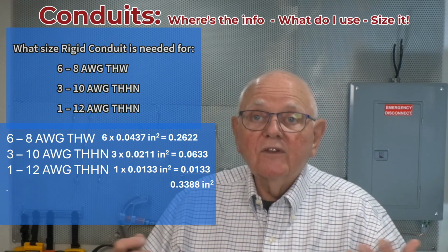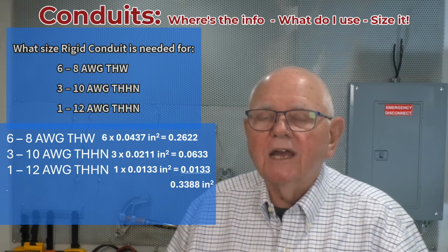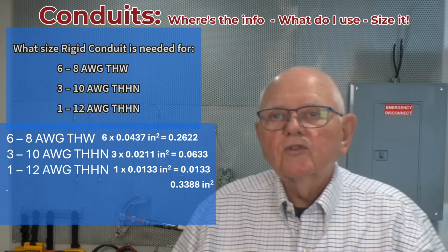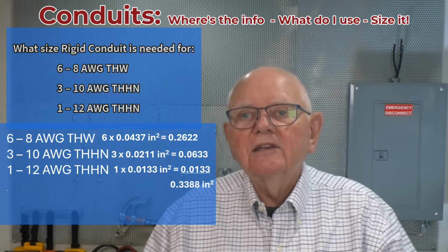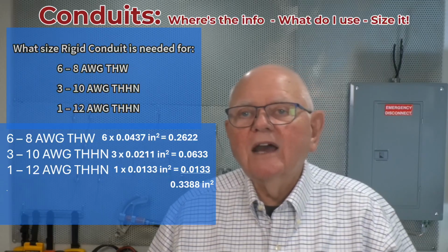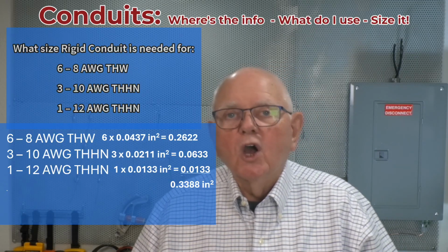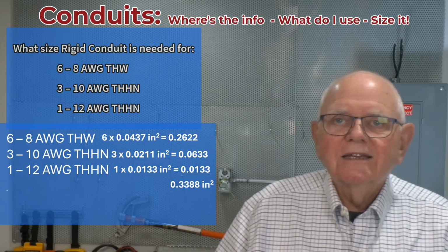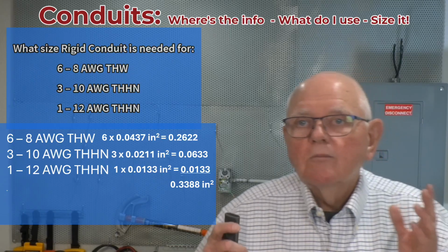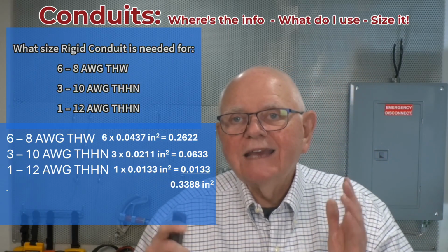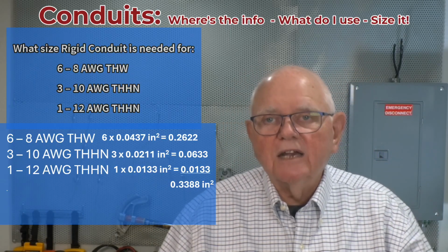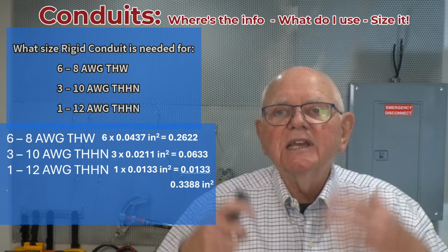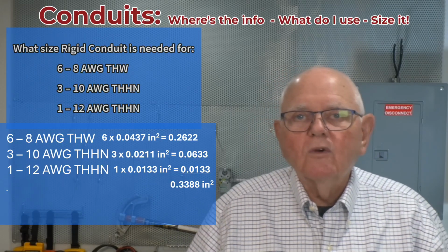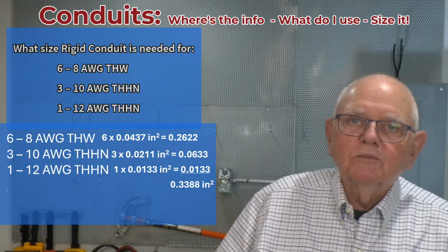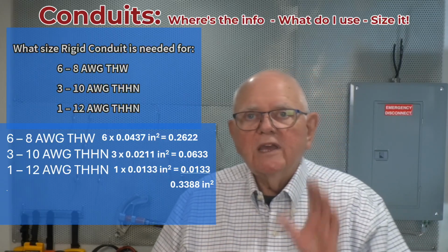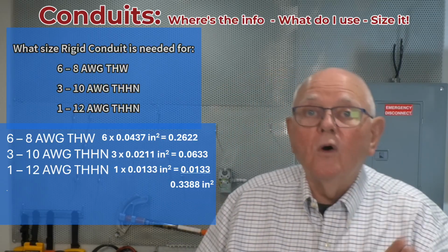So now I add the total of those 3 conductors up, and I come up with 0.3388 square inches. Now I've got to find a conduit then, a rigid conduit that can accommodate those 0.3388 square inches of conductor material and not exceed my conductor fill requirements on that conduit, which would be 40%. So here I can go next to table 4.